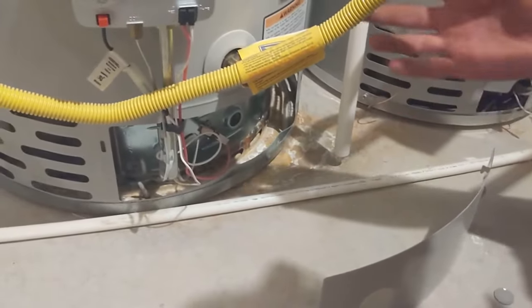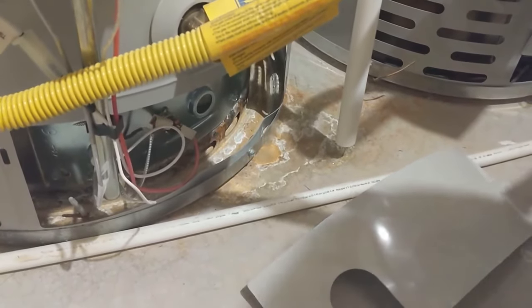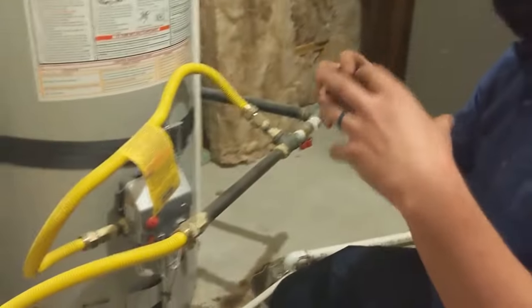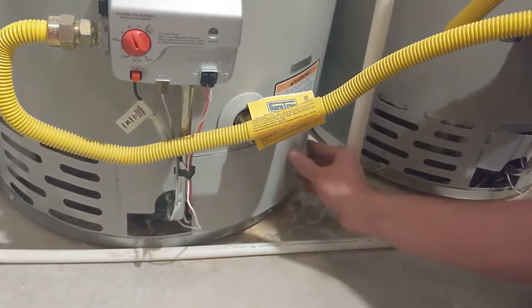The reason you need a new water heater is if the water heater itself started leaking — you'd have water pooling up or a puddle running to your drain. That rust-colored buildup and sediment is most likely from your T&P valve, or it could be condensation from the water heater heating up cold water — it condensates and causes water to escape to the outside of the tank. If you were leaking, you'd have water here. I'm really glad he's not telling us we need a new water heater. He said we just need to flush this one.